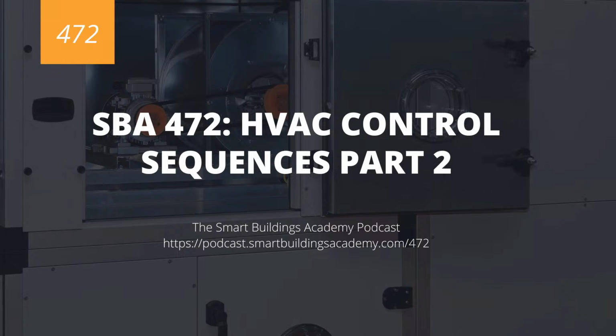Additionally, we have CO2 control, which we will talk about in the air handling section, because you see it occasionally, but you don't see it as often. You don't see CO2 control in a rooftop unit. You typically will see that in an air handler. Although sometimes you see it in a rooftop unit if that rooftop unit is serving like a cafeteria or an auditorium, things like that. But those tend to be the cases. You don't tend to see it when an RTU is serving a classroom or something like that.